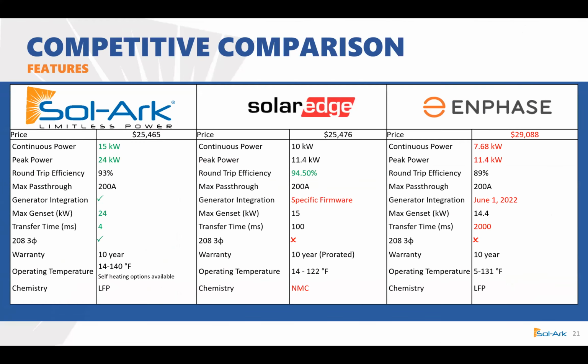Just to give you a small competitive analysis: for around the same price, you're going to get a higher continuous AC output by 5 kilowatts. You're going to get about double the rated peak power. A very comparable round trip efficiency, meaning from DC to battery, and then battery to AC. And then we all have that matching pass-through here. Our generator integration has been automatic since we started. We've been working with it for quite a long time. You can even get a 6 kilowatt Honda that's 240, and we can work with that as well.